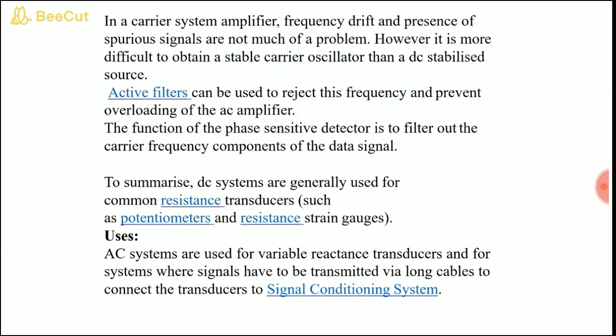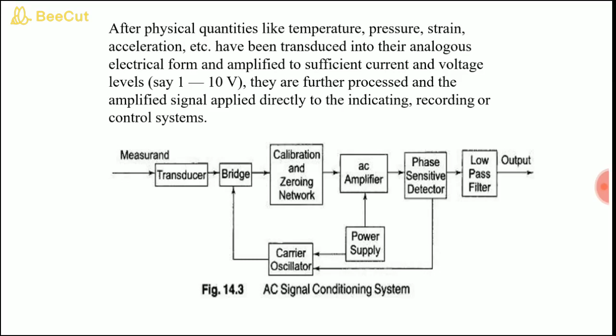Okay, so this is the AC signal conditioning system with respect to DC conditioning, that is the transducer bridge. We have similar components as in DC signal conditioning, calibrating and zero network. We have, instead of DC, an AC amplifier and power supply and a phase sensitive detector. This is the additional circuitry or element which is introduced in the AC signal conditioning system. And the power supply is also common to the AC signal amplifier and carrier oscillator. And the phase sensitive detector is provided as an input to the carrier oscillator and is passed to the bridge circuit. A low pass filter is also provided.